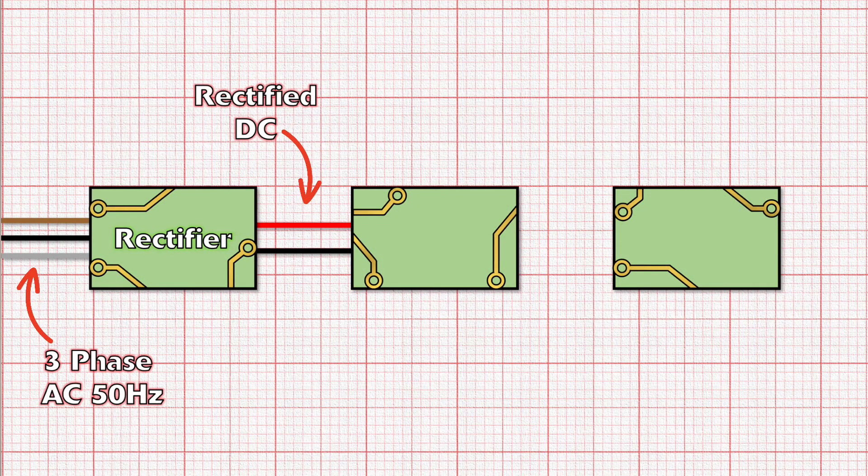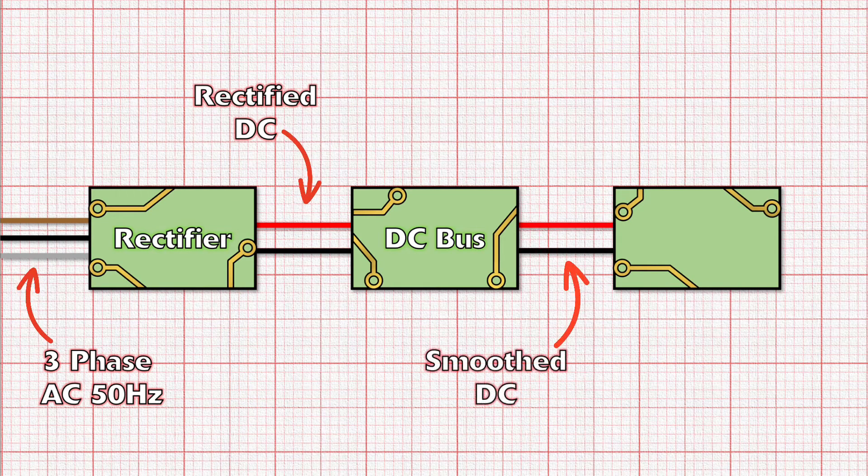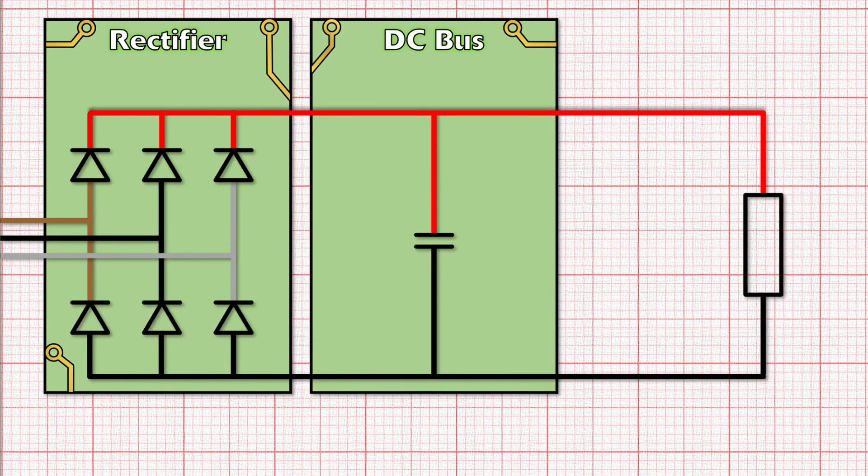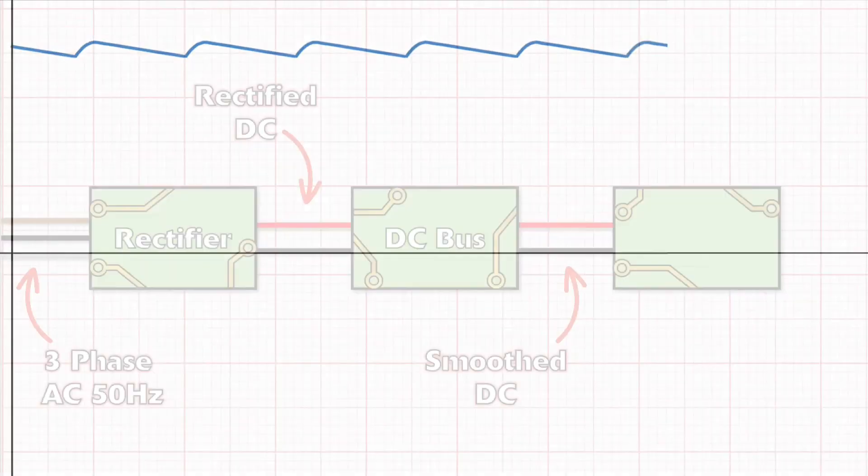This wobbly DC waveform then moves on to the next stage of the internal circuitry of the VFD, which is called a DC bus. All this part does is take that wobbly waveform and smooth it out using capacitors. These charge up with a bit of current while the current is rising, and then as it drops away it releases that current back into the circuit, meaning that the waveform starts to look smoother.